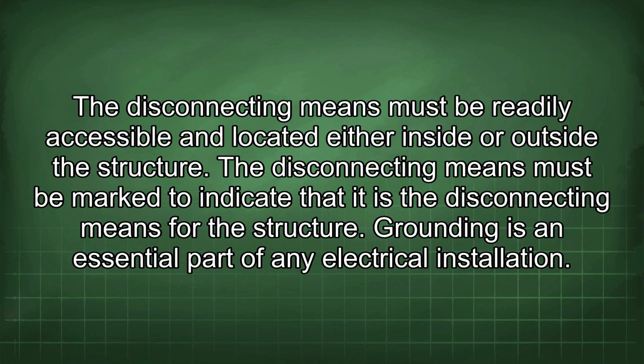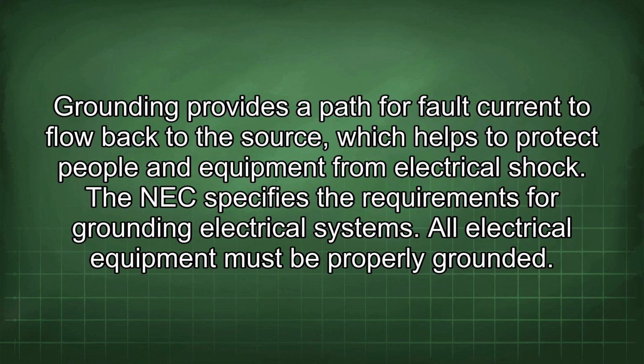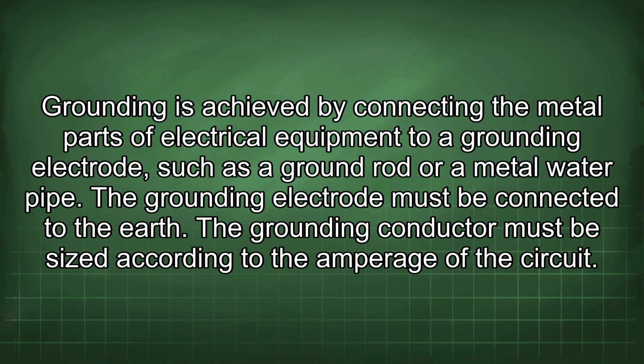Grounding is an essential part of any electrical installation. Grounding provides a path for fault current to flow back to the source, which helps to protect people and equipment from electrical shock. The NEC specifies the requirements for grounding electrical systems. All electrical equipment must be properly grounded. Grounding is achieved by connecting the metal parts of electrical equipment to a grounding electrode, such as a ground rod or a metal water pipe. The grounding electrode must be connected to the earth. The grounding conductor must be sized according to the amperage of the circuit.